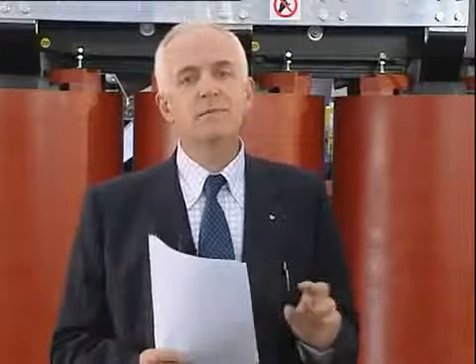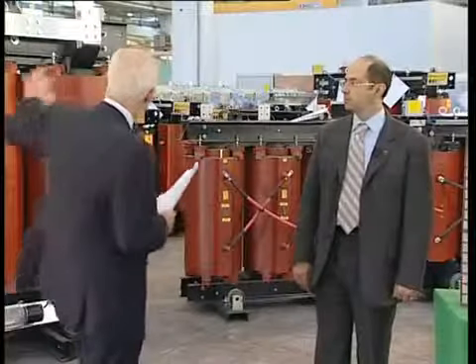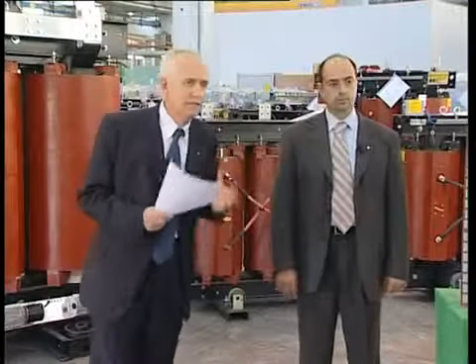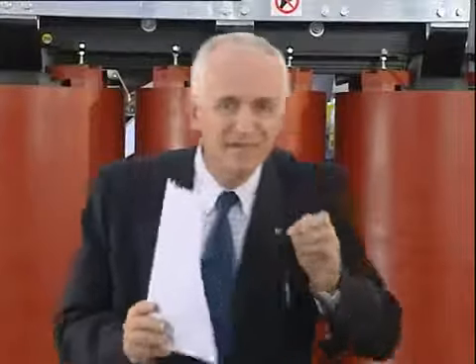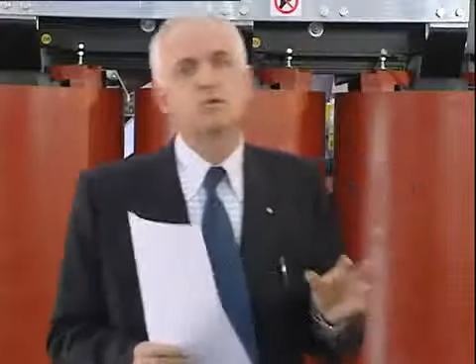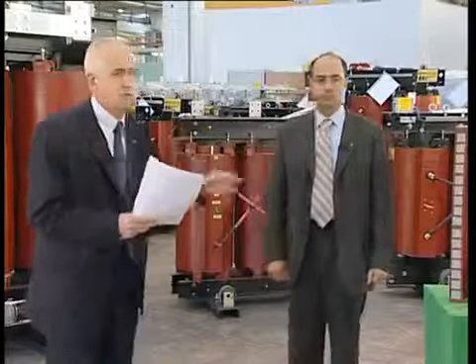In order to verify Mr. Marini's statement regarding the poor quality of some resin-insulated low-medium voltage transformers produced by, say, not very serious manufacturers, we placed behind us some EDM transformers and some of those poor-quality transformers. In the latter, obviously, the brand has been hidden. We are thus going to carry out a comparative analysis of the various products. If you agree, I would like to focus our comparison on the two quality aspects you previously mentioned, i.e., reliability and operating efficiency.